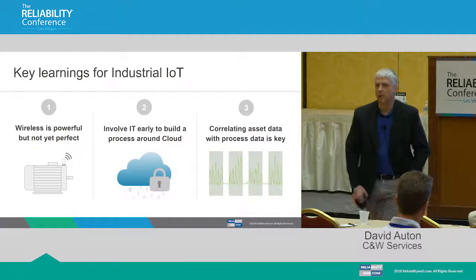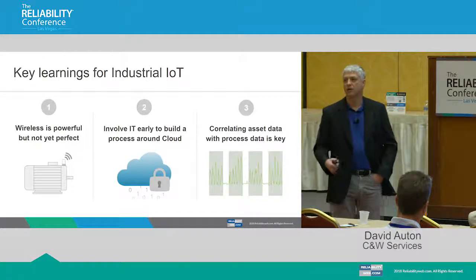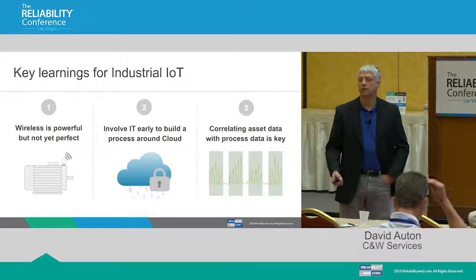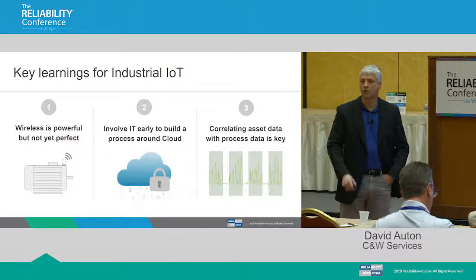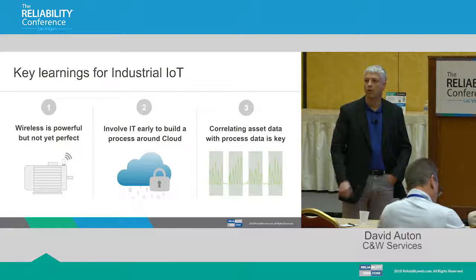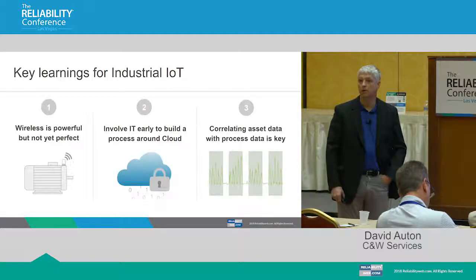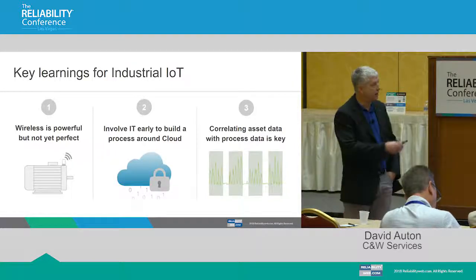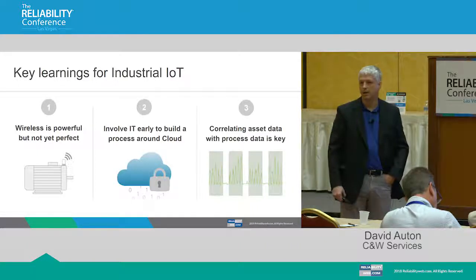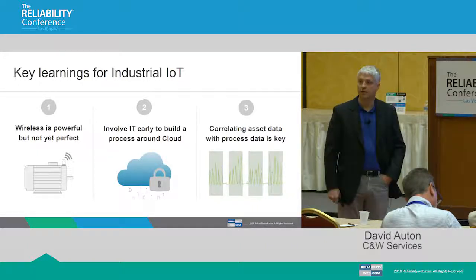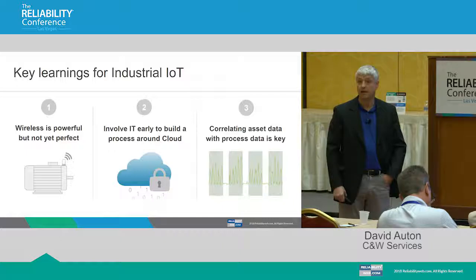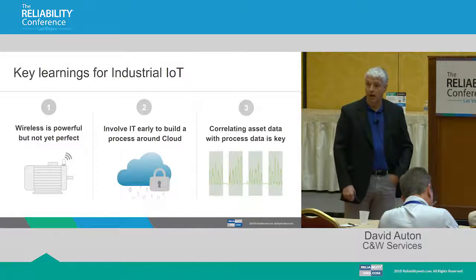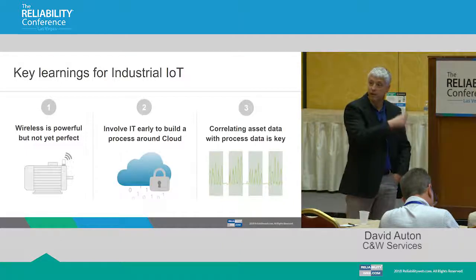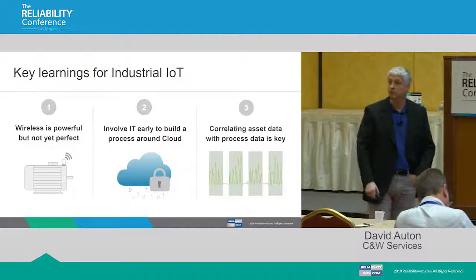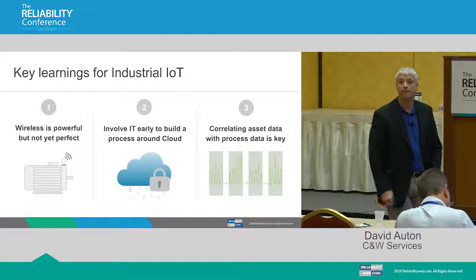My premise is, if the unit is in distress, I should have someone knowledgeable do an overall assessment and find out what's really going on by the time you need a service call. The advantage of the cloud and virtual piece is, if I'm seeing something odd and can't find anything wrong, they can help me further analyze it and say, those are the harmonics of the fan, you might have a fan out of balance, or similar. That really helped as well.